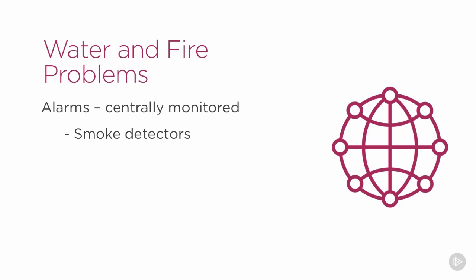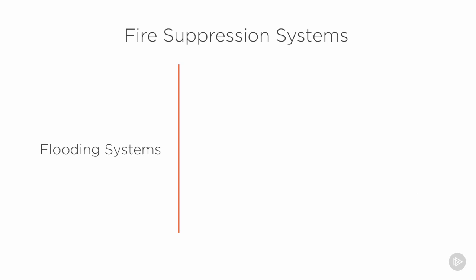When we install smoke detectors, we don't just put them in a server room, but we'll also put them in ventilation ducts and other areas to try to pick up if there's any contaminants or smoke, even coming in from other areas of the building as well. We put in water detectors to pick up in the case of flooding or broken pipes. And then we, of course, if there is a fire, try to put it out.